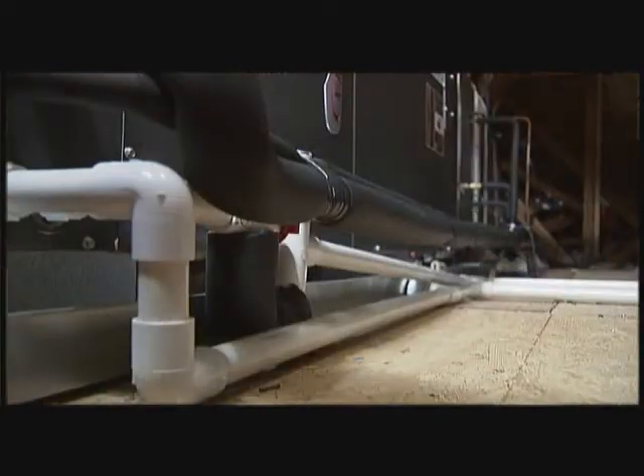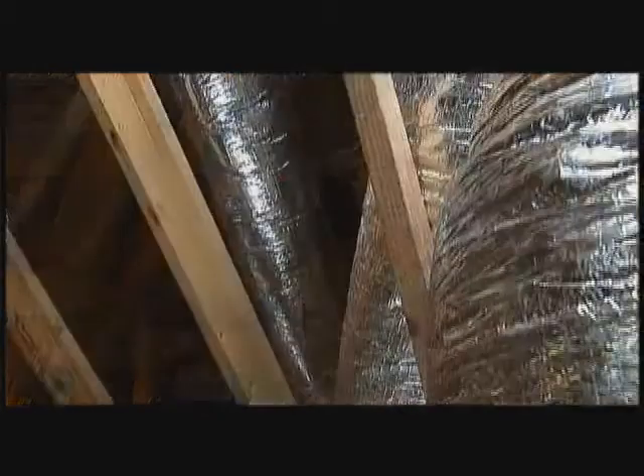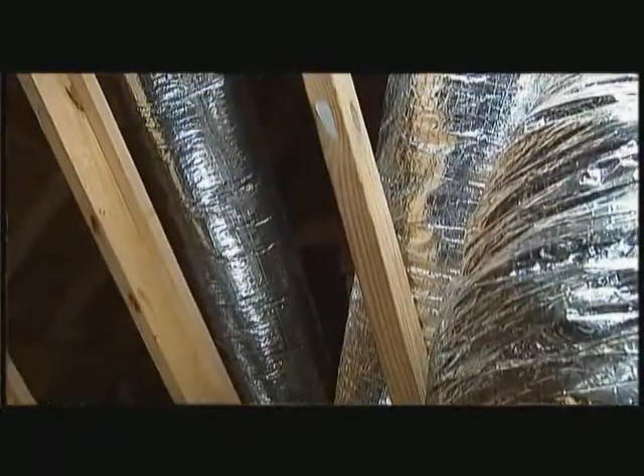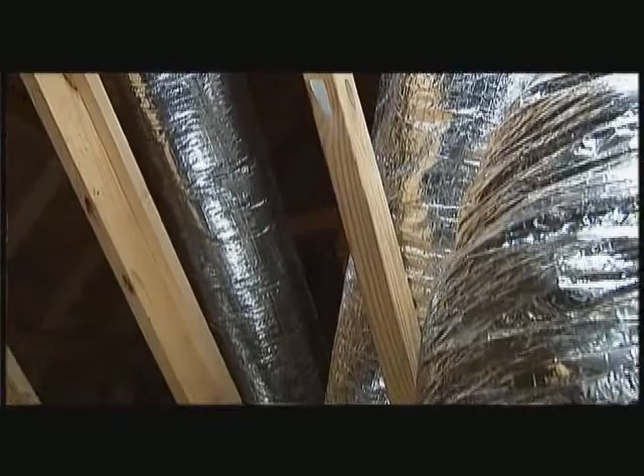So it's a good idea to come up here, look around, look in your condensate pans. If your filtration is up here, inspect it and see if it's dirty and needs to be changed out, and just see if there's any maintenance that needs to be done. Even during the summertime, it wouldn't be a bad idea to come up and look around and see what's going on. Just check your ductwork, because even though ductwork is a static thing and doesn't generally move, as your system comes on and off, the pressures change in your ductwork and it can come loose.